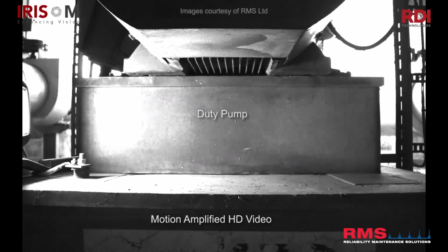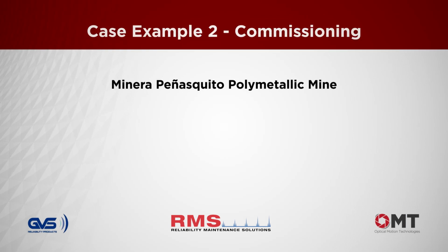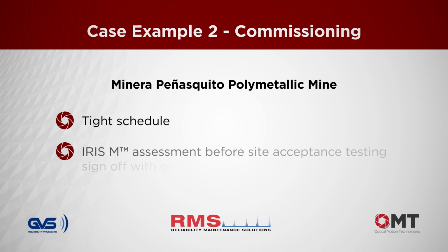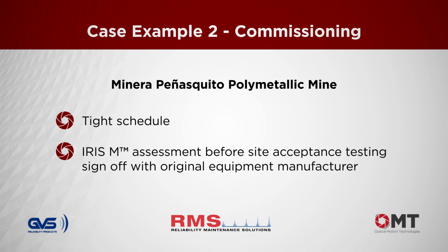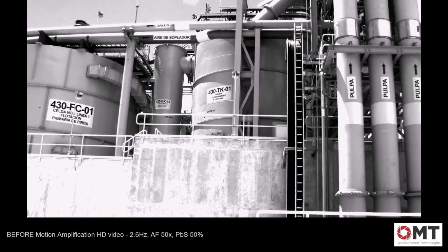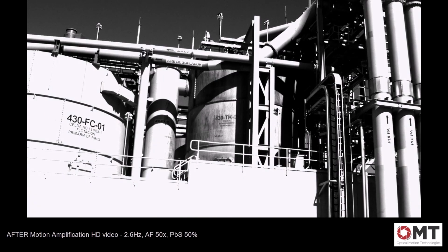Goldcorp purchased the IRIS-M for the purpose of commissioning the new Minera Penasquito facility in Mexico. They were on a tight schedule to bring the new equipment online. Acceptance testing of all new assets included an assessment using IRIS-M before site acceptance testing sign-off with the original equipment manufacturer. This was a tank that they caught vibrating with the IRIS-M. They notified the original equipment manufacturer of the issue, and the OEM stated there was no problem with the tank. Upon seeing the tank in the MA video, the OEM immediately acknowledged the problem and redesigned the tank.